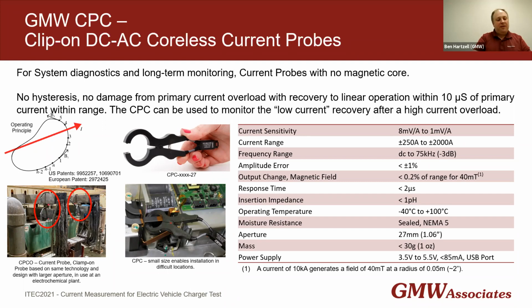Another example of a harsh environment where CPCs and CPCOs are commonly used: we see them at transit agencies measuring high voltage lines, high current conductors for bus or light rail, either as quick diagnostics or as long-term redundant monitoring. The CPC and CPCO both have pretty high ranges, starting at 250 amps for the CPC, up to models at 2,000 amps. The CPCO has models up to 16 kiloamps.